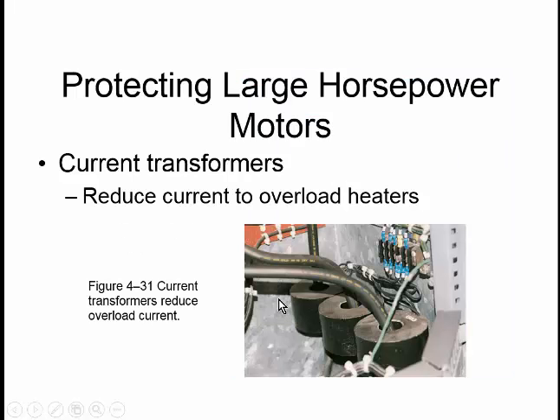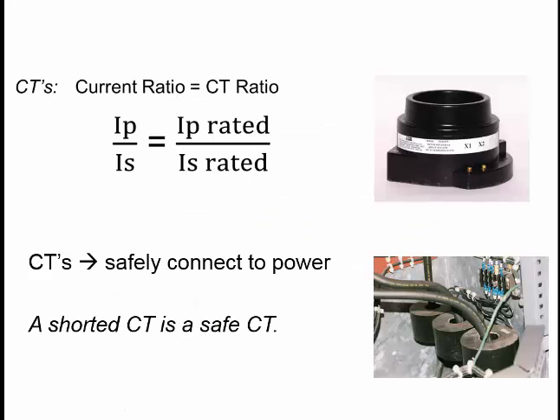On large motors, we'll use something called a CT, or current transformer, which we'll spend more time with later. That current transformer will sense current, and we'll work with that. The way current transformers work is based on their ratio. So with a 200 to 5 CT, if you put 200 amps on the primary, you'll get 5 amps on the secondary. If you put 100 amps, you'd get 2.5. But we'll spend more time with those later. I'm going to make a plug for CTs: a safe CT is a shorted CT. That's totally opposite from what we're used to with, say, voltage transformers. But for now, you'll have to take my word for it, and we'll play with that later.